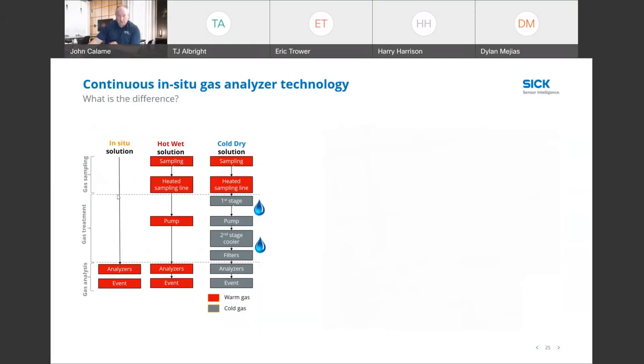But we also manufacture and supply hot wet solutions where we keep the sample above the dew point as we extract it and bring it to the analyzer. It's a heated sample line, umbilical, pump, all the way through the analyzer. It stays hot above the dew point. So it's a robust system for applications that have high particulates and applications that are measuring acids that possibly would condense. But we can do the hot wet strategy, which is extractive, and also cold dry extractive as well. And a lot of the cold dry extractive we use on traditional CEMS measurements to measure NOx.